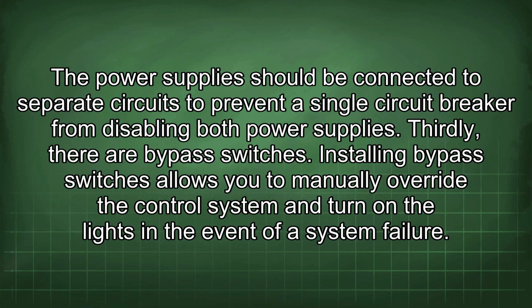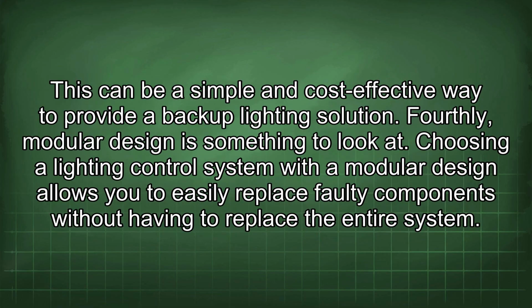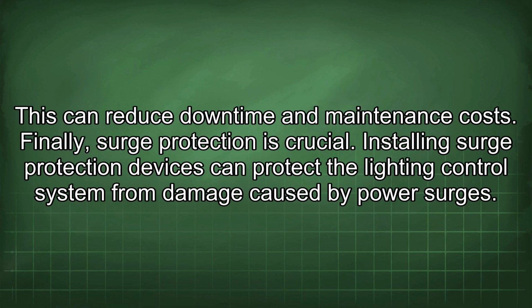Thirdly, there are bypass switches. Installing bypass switches allows you to manually override the control system and turn on the lights in the event of a system failure. This can be a simple and cost-effective way to provide a backup lighting solution. Fourthly, modular design is something to look at. Choosing a lighting control system with a modular design allows you to easily replace faulty components without having to replace the entire system. This can reduce downtime and maintenance costs.